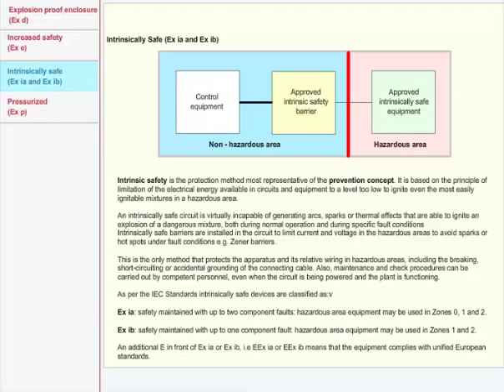the plant is functioning. As per the IEC standards, intrinsically safe devices are classified as Ex ia, safety maintained with up to 2-component faults. Hazardous area equipment may be used in zones 0, 1, and 2. Ex ib, safety maintained with up to 1-component fault. Hazardous area equipment may be used in zones 1 and 2. An additional E in front of Ex ia or Ex ib, that is EEx ia or EEx ib, means that the equipment complies with unified European standards.